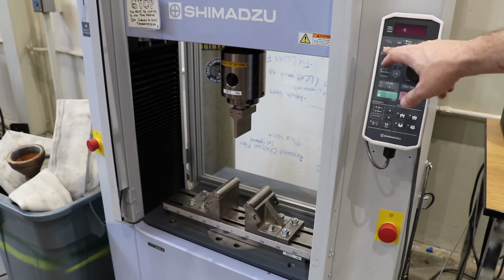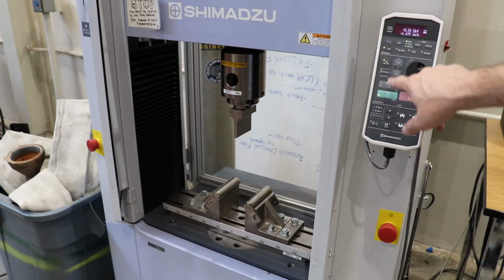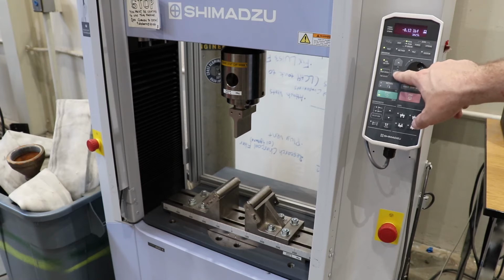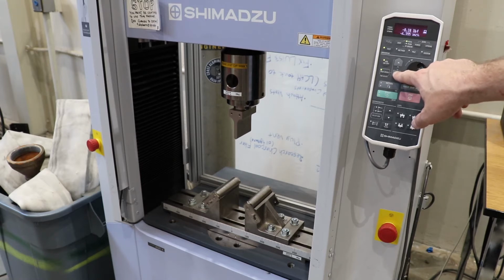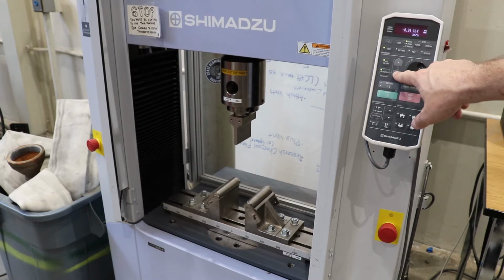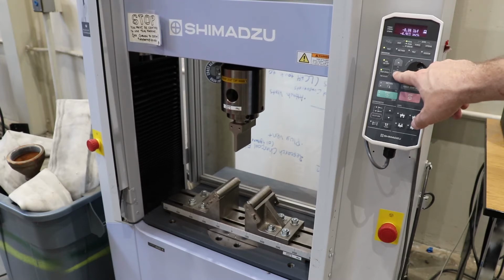Now we will begin to jog the load frame down to the test fixture. To do so, press the Test button, now press the Jog On-Off button and press the High Speed button. Then use the up or down to move the head.